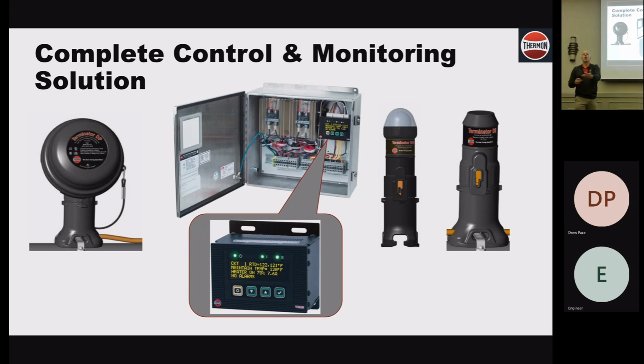But the heat trace doesn't know that you're trying to maintain 150 degrees or 170 degrees. It doesn't know that. It's self-regulating, but self-regulating doesn't mean self-regulating to 170. It just means the resistance of the cable is going to fluctuate in response to temperature. So if you have an RTD in your bundle or on your line somewhere, that RTD goes into the panel and says 170 because that's what it's programmed to. Now you're going to maintain 170 degrees. If your plant goes down and you want to turn off the heat trace because the plant's going down, then that's a set point that you would just adjust in there.